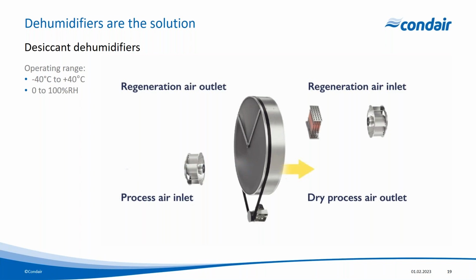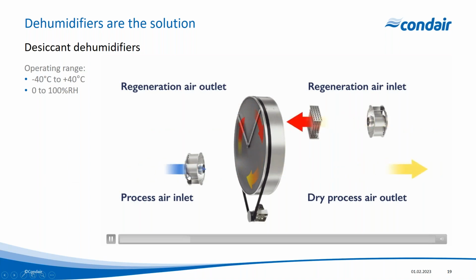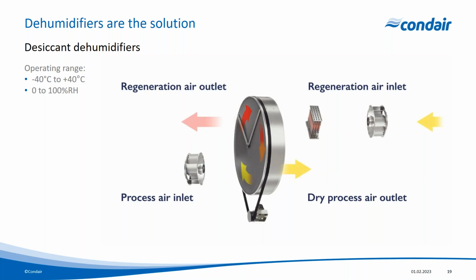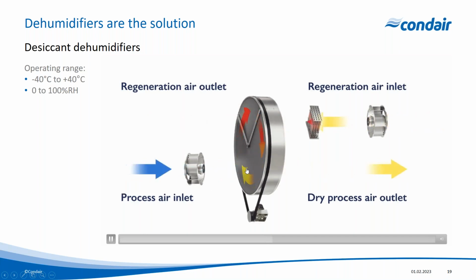So with chill store and cold store dehumidification, we use a desiccant dehumidifier. Here we have our process air coming in from a cold store or a chill store. That process air comes into a dehumidifier, and it hits a desiccant wheel. Now, this desiccant wheel has an incredibly high surface area that captures water molecules in the air in their gaseous state. It holds onto those water molecules, so that air has been dried as it passes over this desiccant wheel. The water molecules have been captured, and we get dry air going back into the cold store.